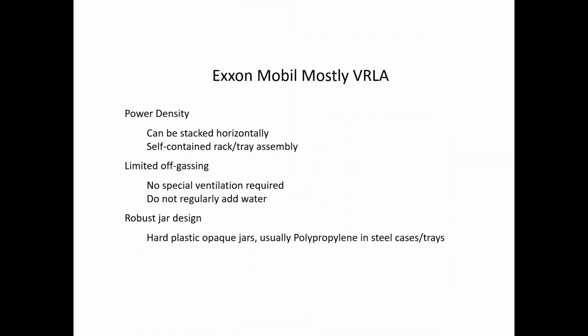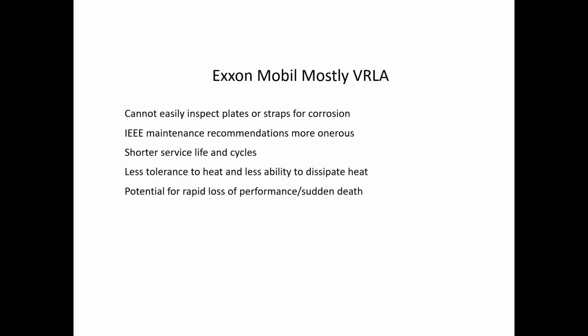So why is ExxonMobil using valve-regulated batteries? Again, the density, and the self-contained rack tray, so there's not another component that has to be assembled. They're usually shipped in their final assembled rack, as it were, in the steel casings or steel cans. Limited off-gassing. You don't need special ventilation. Typically, you don't need hydrogen detection incorporated with a valve-regulated battery install. You do not regularly add water to the battery. As a matter of fact, it's very difficult to do that. And the robust design, the hard plastic: you can drop one of those batteries and you're not going to have free electrolyte spill all over the room.